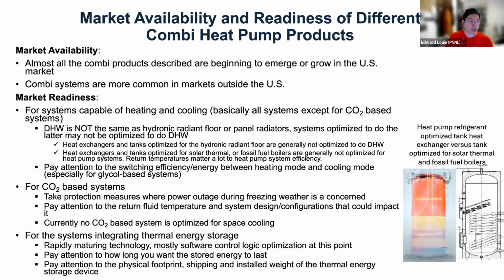So in terms of market readiness, for the systems capable of heating and cooling, so basically all systems except CO2-based systems, some things to really think about are heat exchangers. Heat exchangers and tanks that are optimized for hydronic radiant floor are generally not optimized to do domestic hot water. The reason is that the temperatures in the radiant floor are not going to be 120 or 130 degrees. They're much colder, generally in the 80, 85 degree range. But if you want 130 degree water, those heat exchangers will result in very high liquid line temperatures, and that results in the heat pump operating not very efficiently.